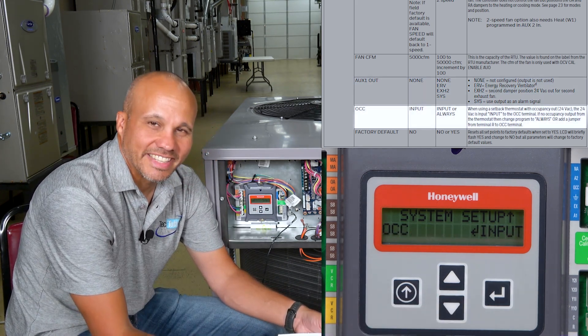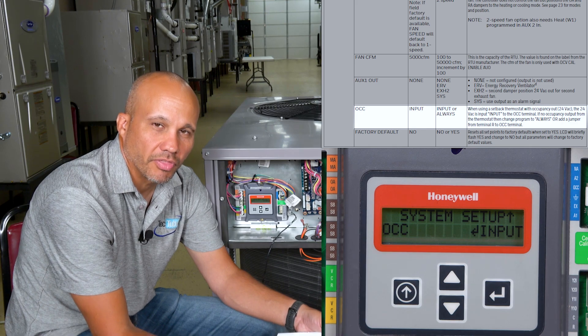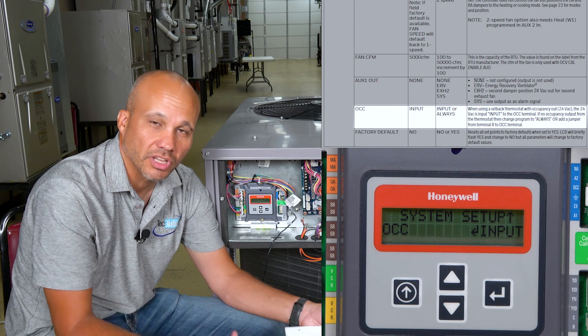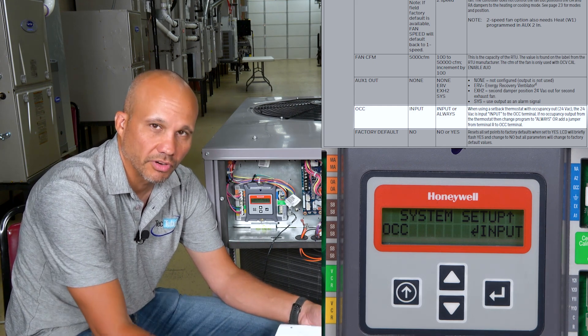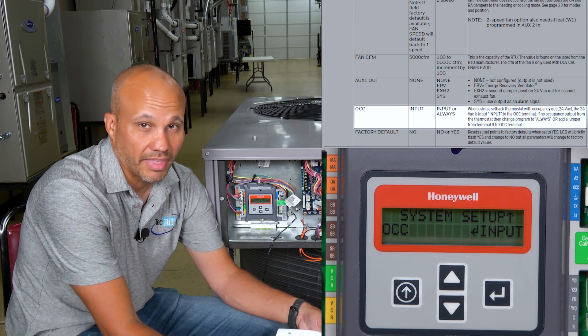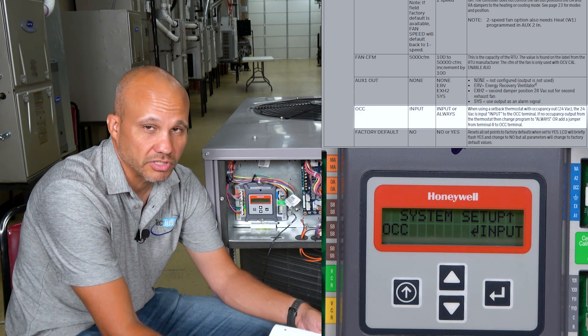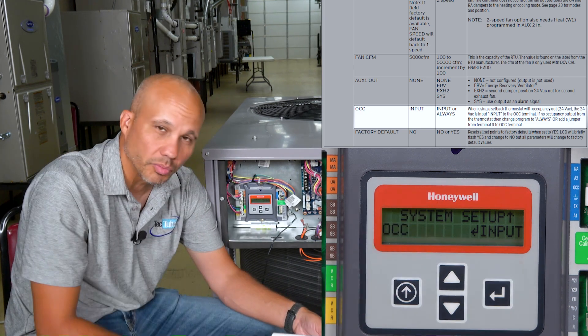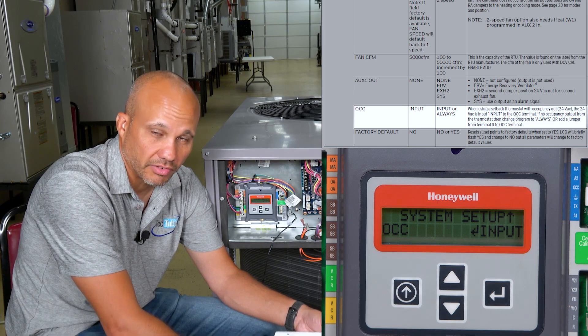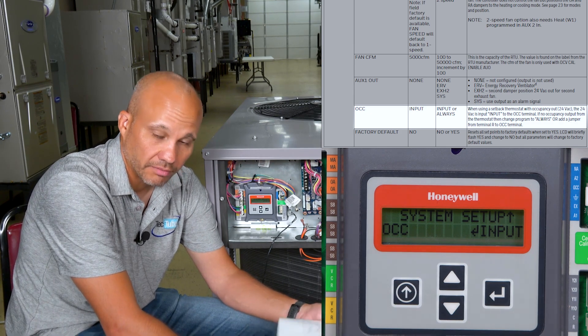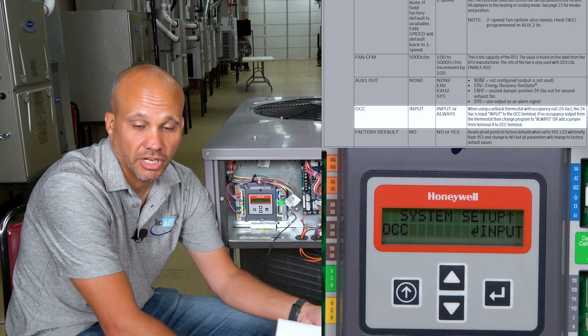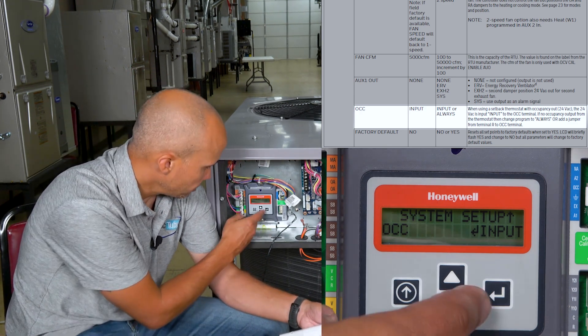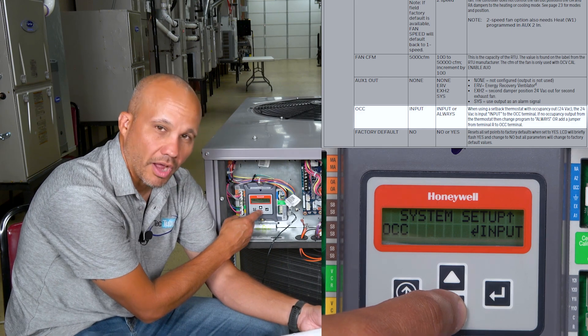Occupancy: the default is Input — it's looking for an input from a thermostat, building automation system, motion sensor, or whatever can tell when the building is occupied versus unoccupied. That is required by code in almost every state. If for some reason you didn't have that, you'd want to change this to Always, so it's always running the schedule 24/7 and always provides ventilation air. Input is the normal scenario if you're going to wire to it correctly.